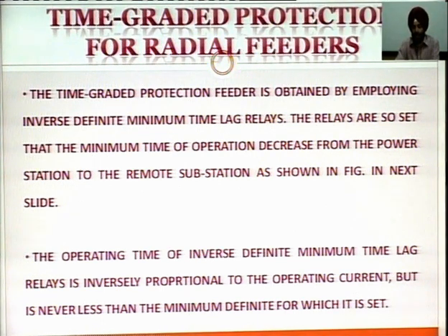So next slide. The operating time of inverse definite minimum time lag relay is inversely proportional to the operating current but is never less than the minimum definite time for which it is set. So its time should not exceed a certain time.